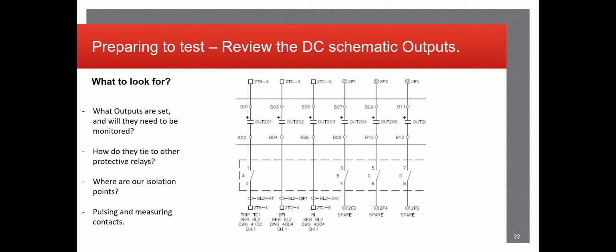DC schematic outputs. This is where you won't be utilizing the spare output contact. You're actually going to be making sure that the specific output is operating based on whatever test you're running. The isolation points, again, sometimes depending on the scheme, for example here, your trip coil 1 output and the rest of the spares actually lead to knife switches, but in this case, for the breaker failure initiate and the reclose initiate, they actually don't hit anything and they go right out to the terminal blocks and then possibly to another panel.